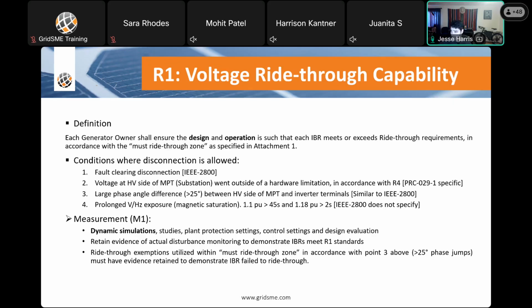So if you do go through one of those voltage ride-through zones or zones of high voltage or low voltage, and your IBRs ride through, you need to be able to prove that through the data that you collect. And then ride-through exemptions utilized within the must ride-through zone in accordance with point 3 above must have evidence retained to demonstrate the IBR failed to ride through.